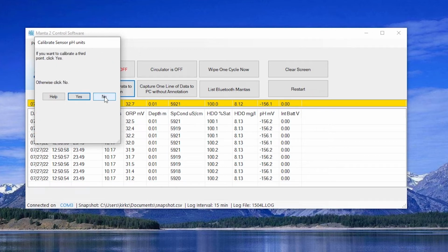The Manta will ask you if you wish to calibrate a third buffer. We don't recommend calibrating a third point unless required by your SOP. If you wish to calibrate a third point, simply follow the same procedure used in the first two buffers. If not, click No. On the next screen, you will find the sensor response factor. The SRF is Eureka's unique way to show you how close your calibration is to that of a typical sensor. An SRF between 80 and 120 is acceptable.